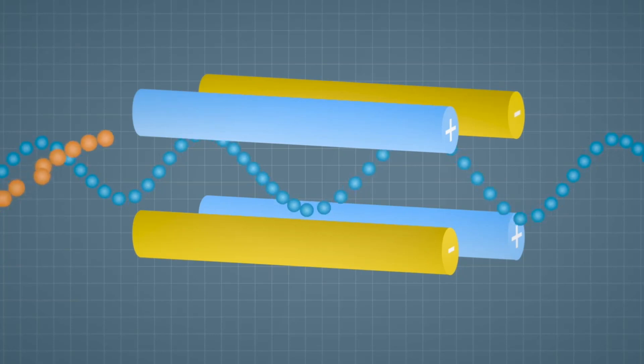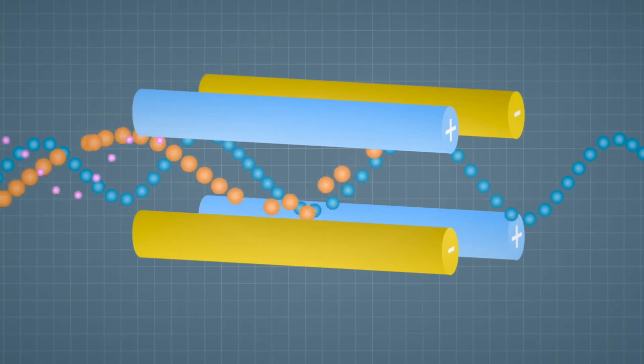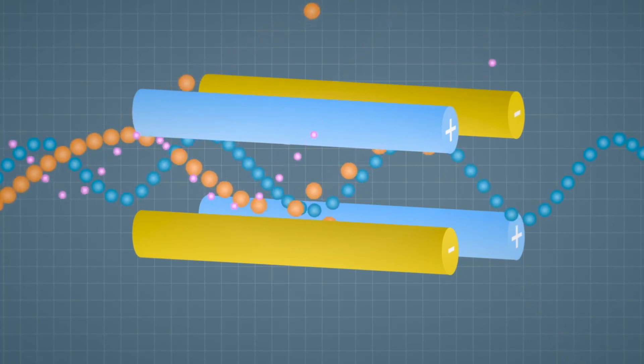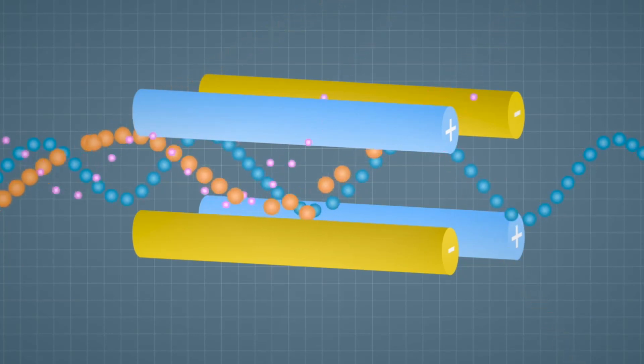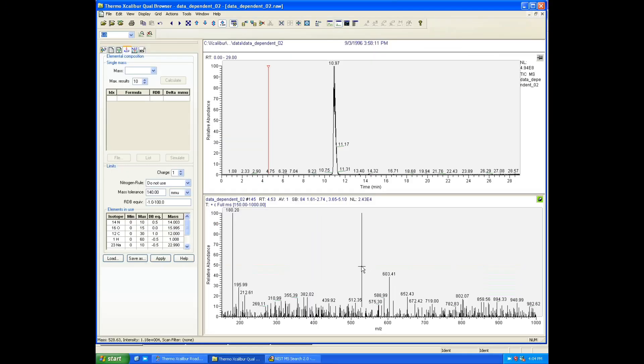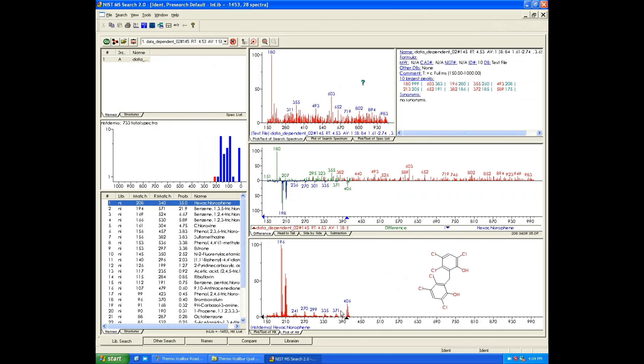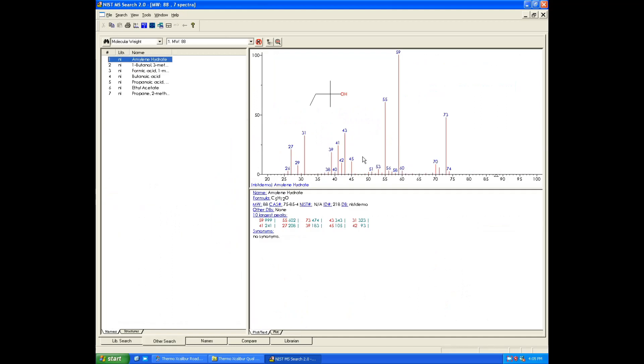This creates an electric and magnetic field arranged in such a way that the ion can be selected. Since they should theoretically have the same electric charge, the mass is the only property affecting their trajectory. The selected ion that passes through the quadrupole can then reach the detector where it creates a signal to be amplified by the computer. This unit can read between 17 and 2,000 atomic mass units with a scan speed of 12,000 AMU per second. This instrument is better used for large organic chemicals, and the software is very good at identifying them despite the fragmentations, multi-charged species, and other adduct ions.